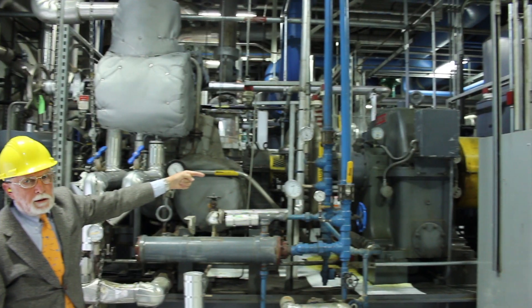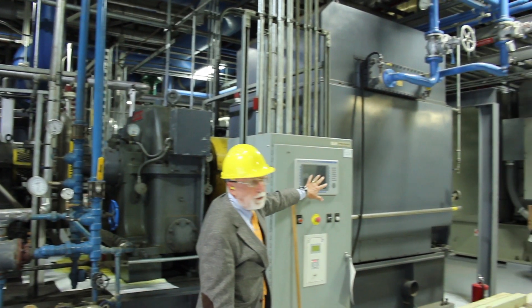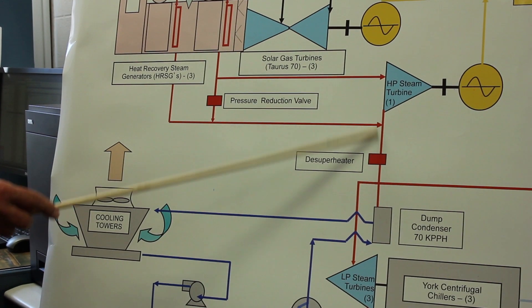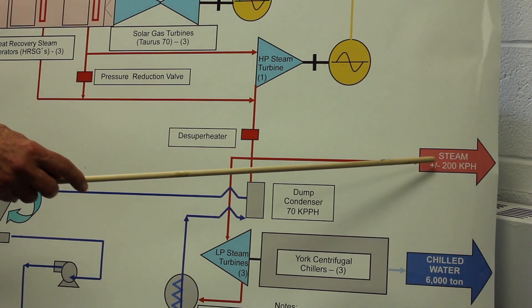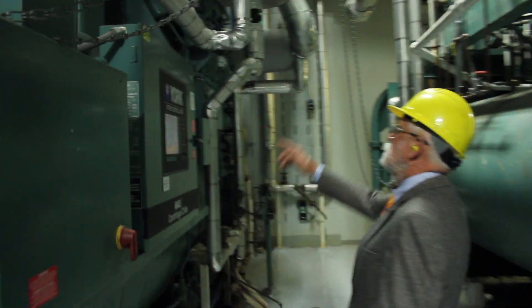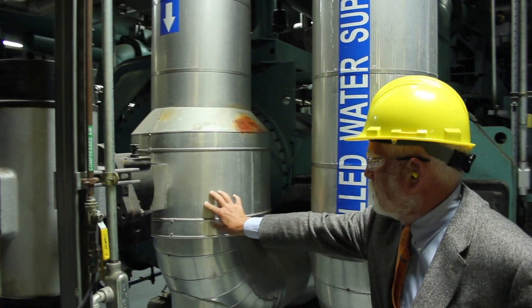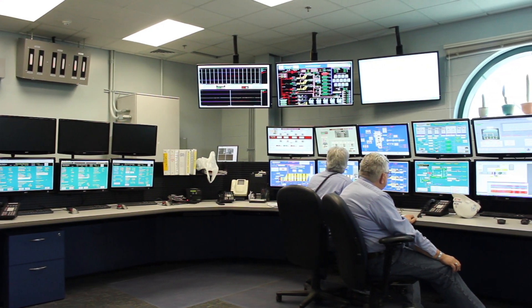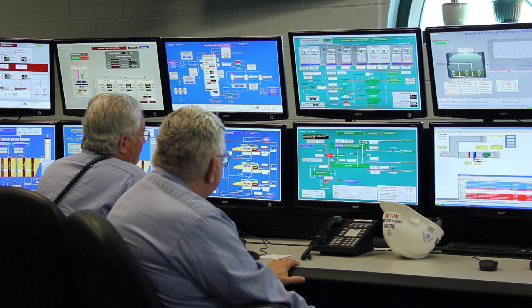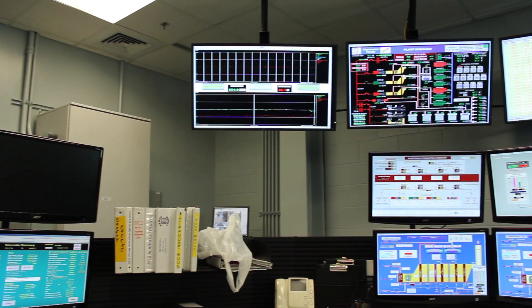Some of the hottest steam then goes to a steam turbine to produce more electricity. This cooperative combination of the gas turbines and the steam turbine is called a combined cycle power plant, which as a combined unit almost doubles plant efficiency. The HRSG steam is also used for heating campus buildings, kitchens, and laboratories, and also powers smaller steam turbines on refrigeration units to produce chilled water for air conditioning units all over the campus. Thus, one unit of fuel in the co-generation plant produces electricity, heating, and cooling, rather than using three units of costly fuel if produced separately in the old pre-2006 way.